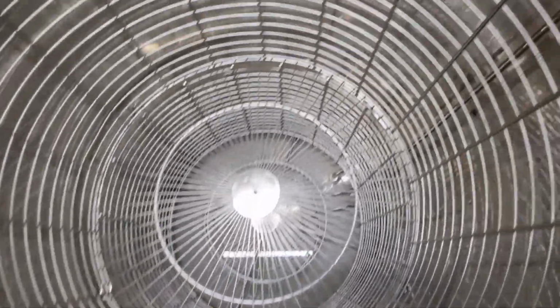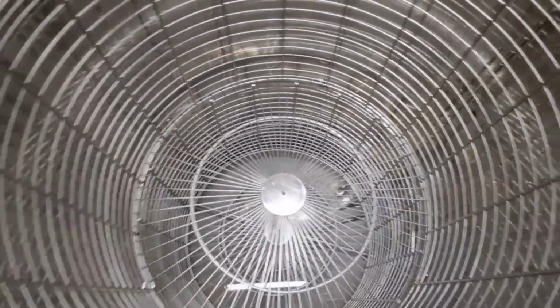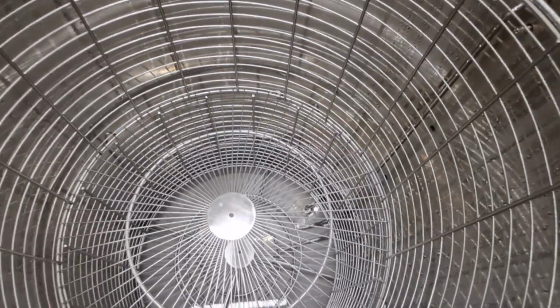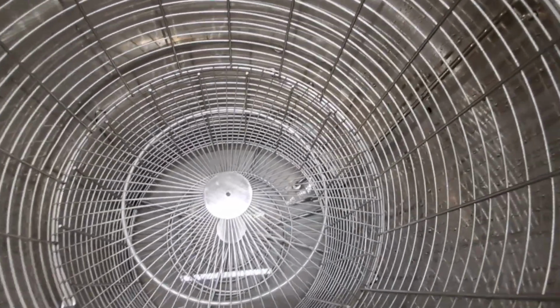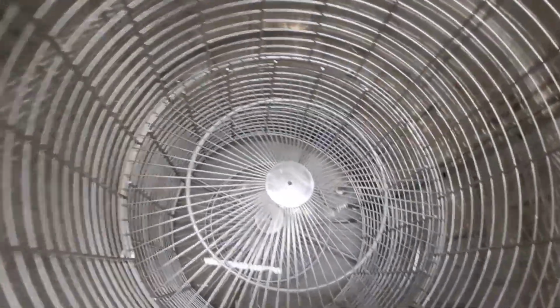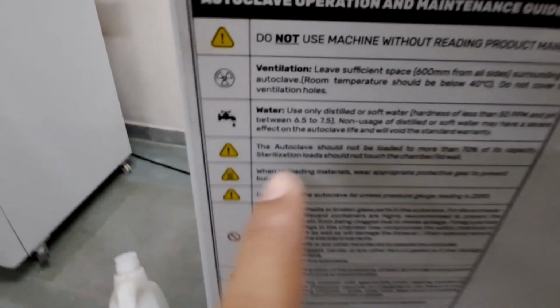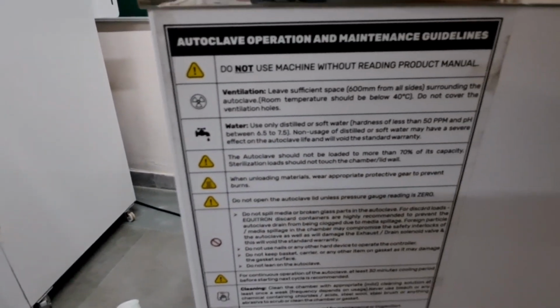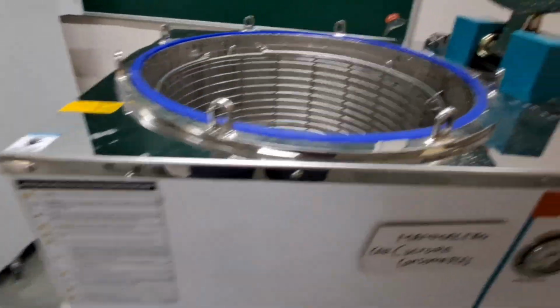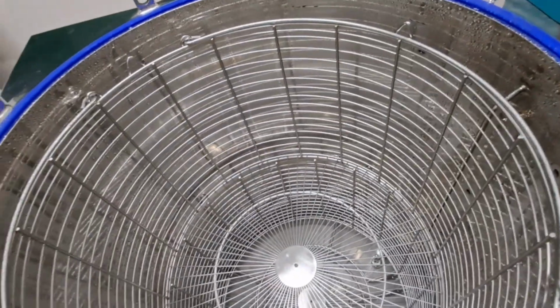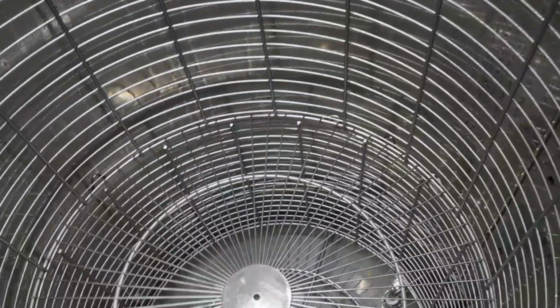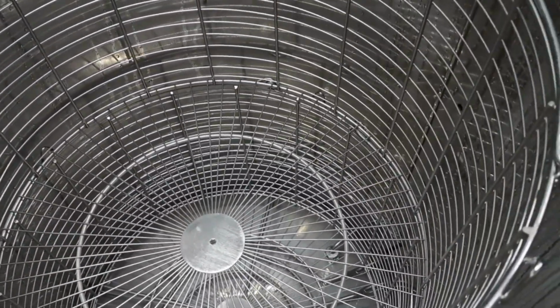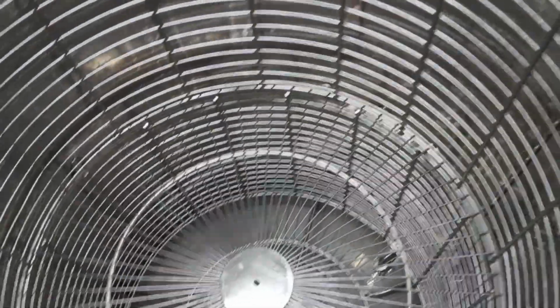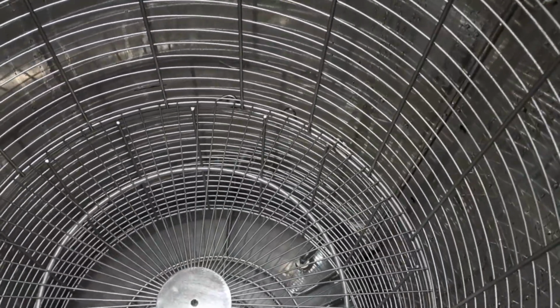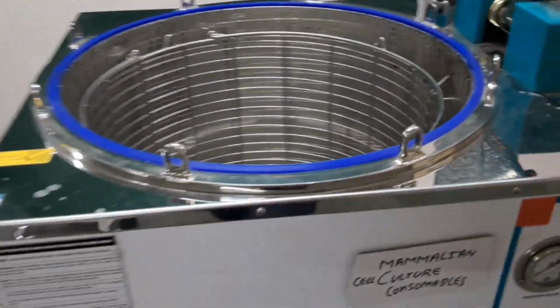And there are two trays, you can keep your utensils here, and you have to fill it with distilled water. But if distilled water is not available, normal water will be fine. But the thing is, it should be of 6.5 to 7 pH and 50 ppm. However, it is not very necessary because you will be working in high pressure, high temperature also, so it will be completely fine. If you just want to kill the bacteria and sanitize it, contamination free, then it is completely fine. So let's move to the next step.